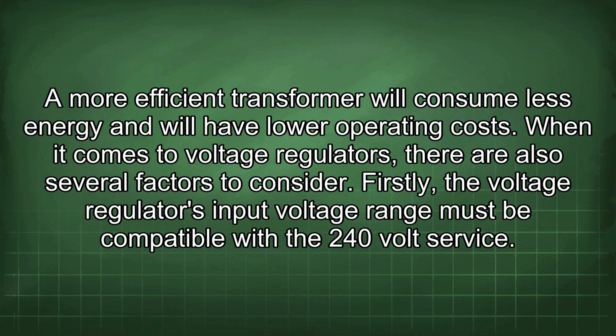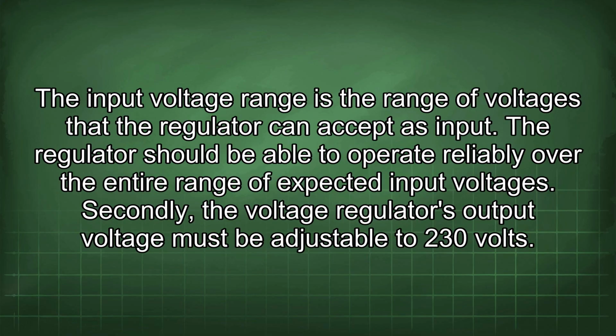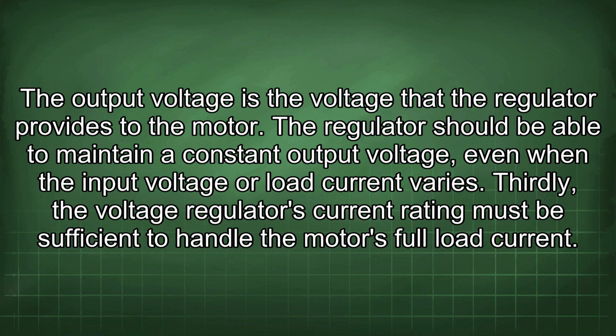When it comes to voltage regulators, there are also several factors to consider. Firstly, the voltage regulator's input voltage range must be compatible with the 240-volt service. The input voltage range is the range of voltages that the regulator can accept as input. The regulator should be able to operate reliably over the entire range of expected input voltages. Secondly, the voltage regulator's output voltage must be adjustable to 230 volts. The output voltage is the voltage that the regulator provides to the motor. The regulator should be able to maintain a constant output voltage even when the input voltage or load current varies.